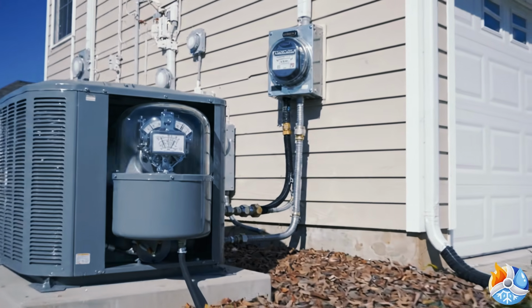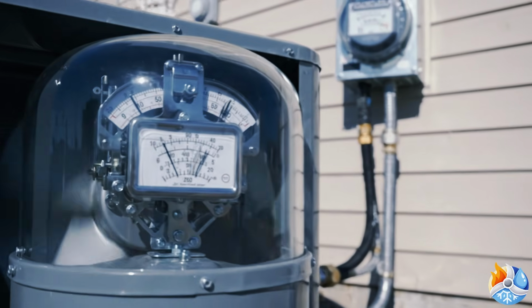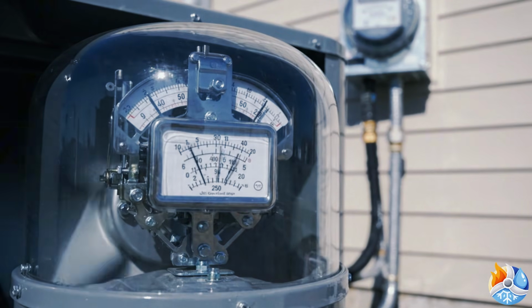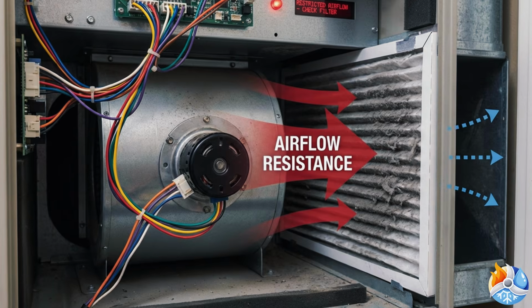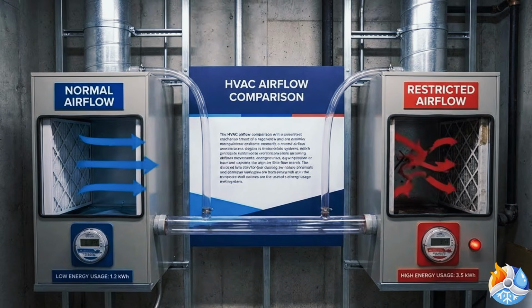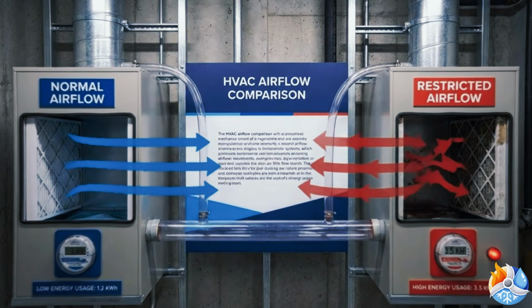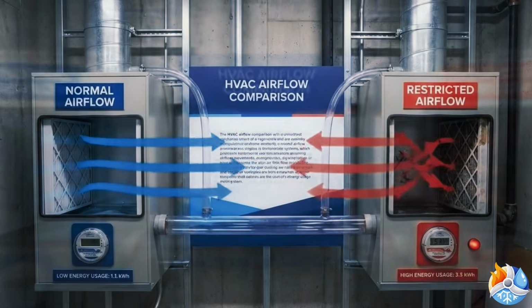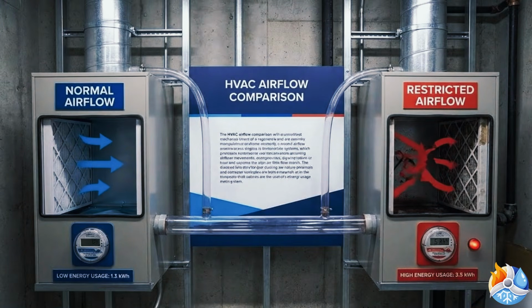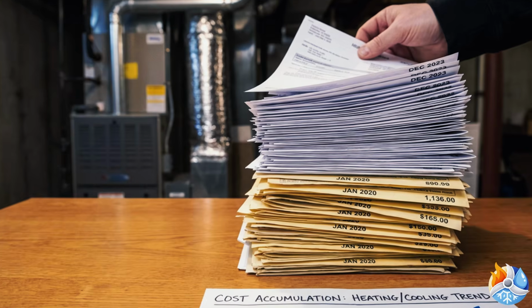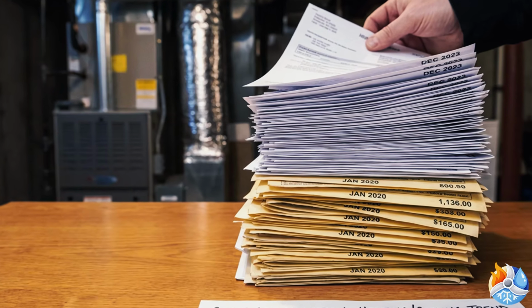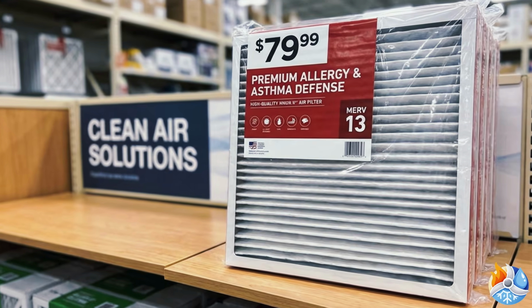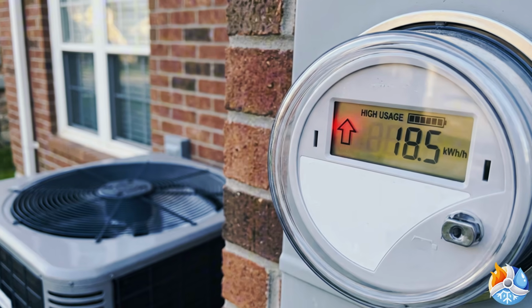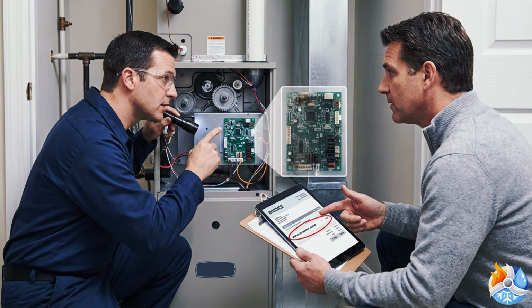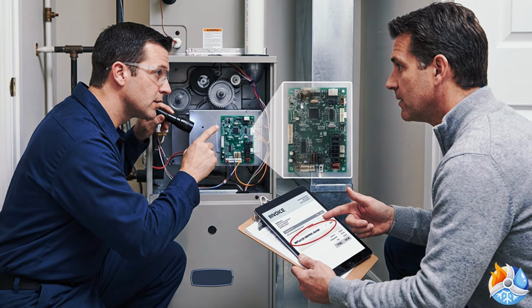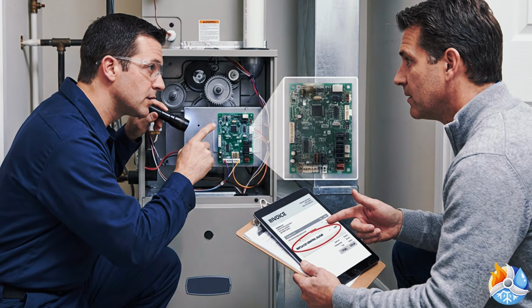There is one more cost that is invisible until it is not: electricity. When your blower fights resistance, it draws more power. Studies have shown that high-rated filters and systems not designed for them can increase fan energy use by 15% or more. That adds up month after month on your utility bill. You are paying more for the filter. You are paying more for electricity. And you are accumulating equipment damage that eventually shows up as a repair bill with no obvious cause.